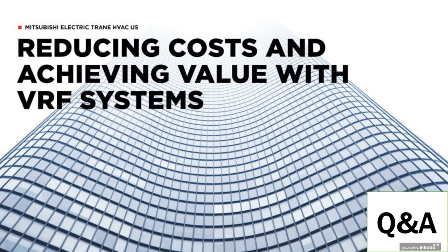Really, that's one of the hallmarks of VRF technology: flexibility. If you plan for your building, you assume what tenants you want to occupy it. Let's say you're building an office building. You assume that there's going to be some kind of closet or room for servers or data equipment. You would factor that into your upfront calculations for the outdoor units. And really, in one of the examples that Jose walked through, you're sizing the outdoor units for the total potential load of the building, knowing that with a VRF system, you can modulate your connected capacity, so to speak. If you size it for 100%, it doesn't always run at 100%. It may run at 110 or 120 for a short period of time, but you want to take that into account when you're setting the outdoor units.